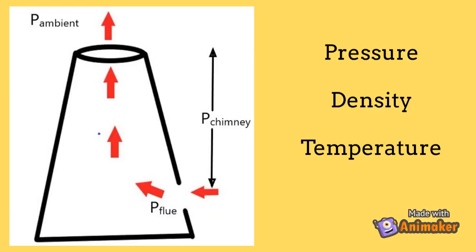The question is: what drives the flue gases from the bottom part of the chimney to the topmost part where it gets dispersed with the ambient air? Whether it is pressure difference, density difference, or temperature difference between the ambient gas and the flue gas — the answer is it is ultimately the pressure difference between the ambient air and the flue gas that drives the flue gas out of the chimney.